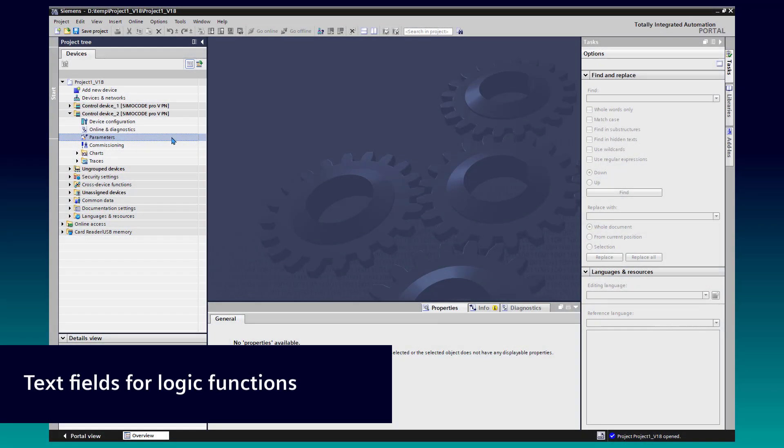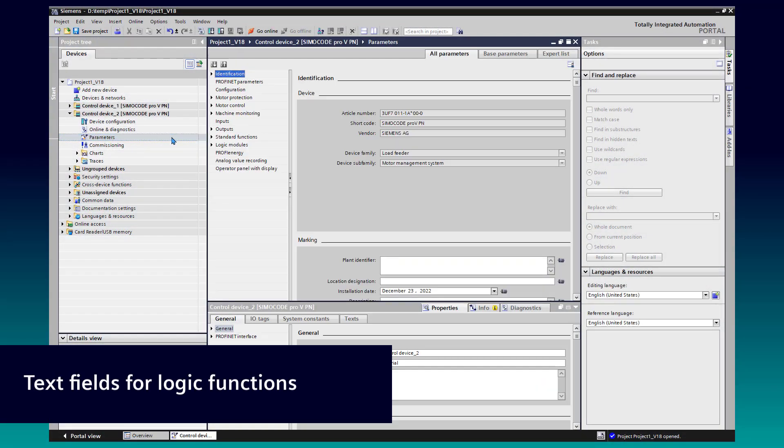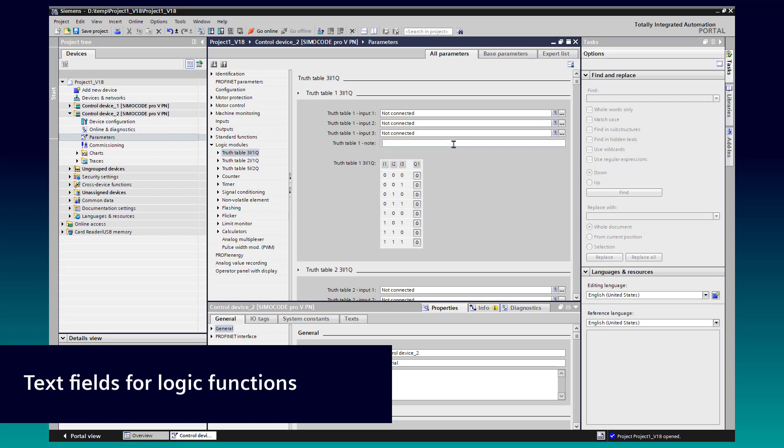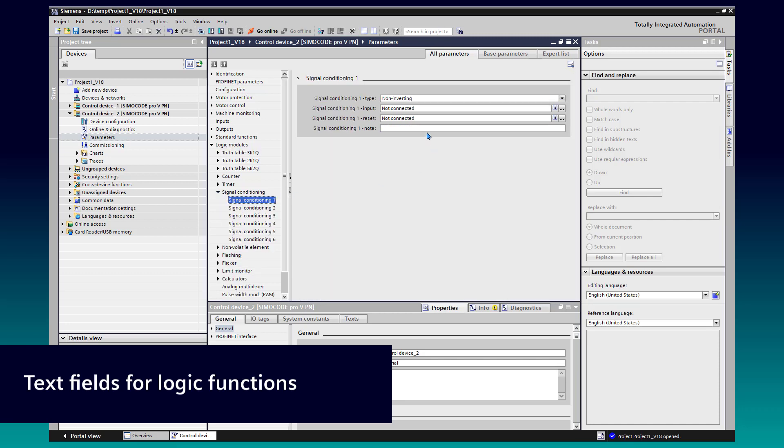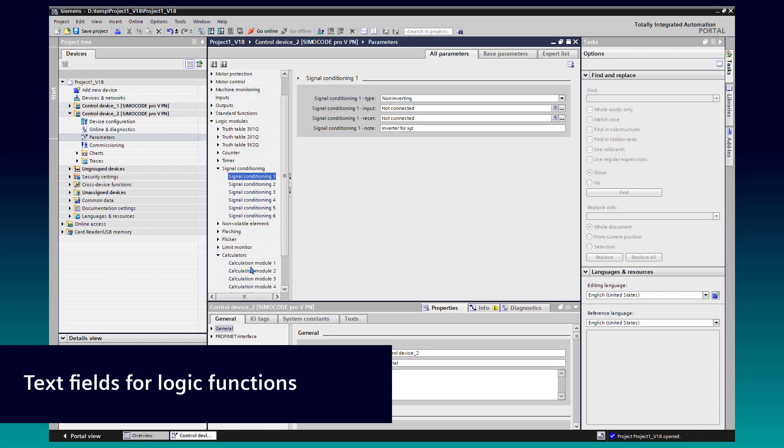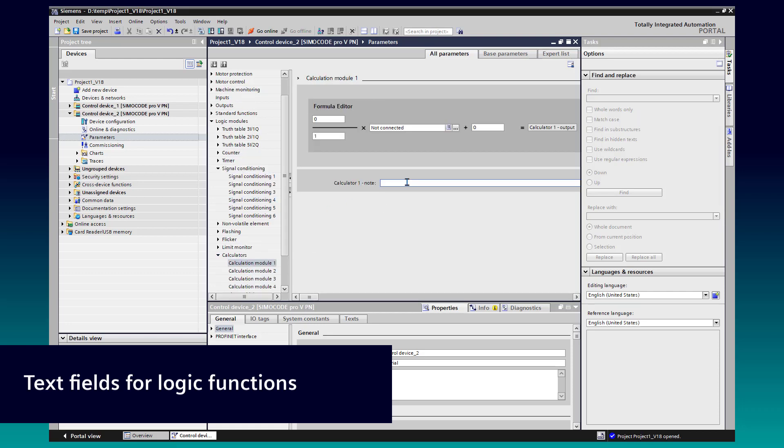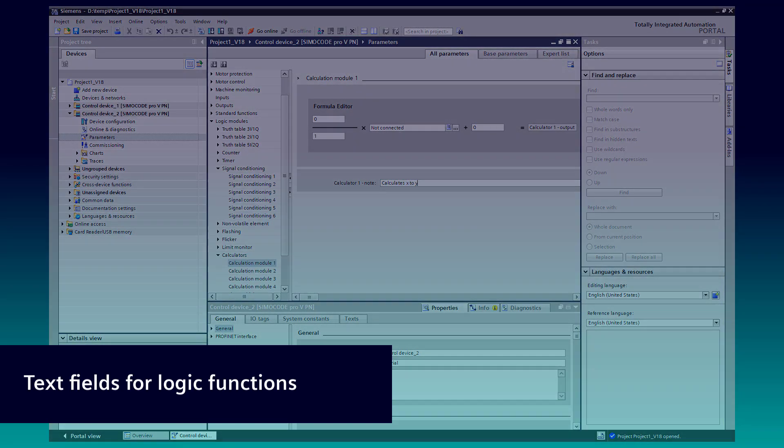Another improvement in SimoCode ES version 18 are new text fields for logic modules like truth tables, signal conditioning, or calculation modules. You can write up to 80 characters here. Keep in mind that these comments are in the offline project only and not stored at the SimoCode device, but they are part of the printout report. This will improve the documentation and understanding of your logic.